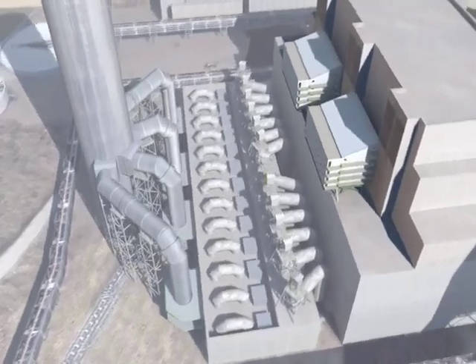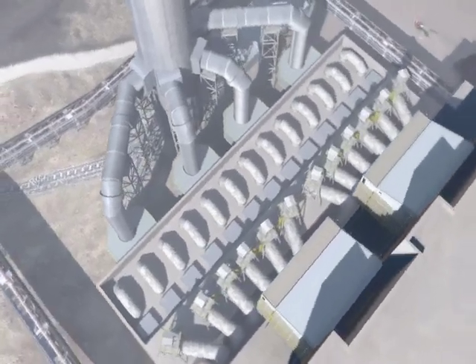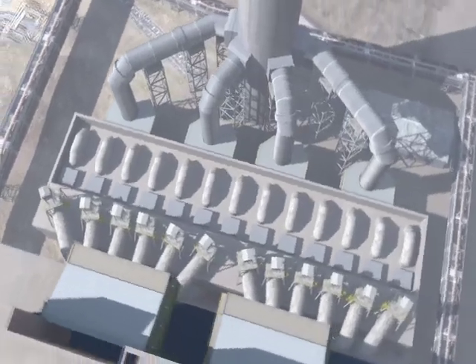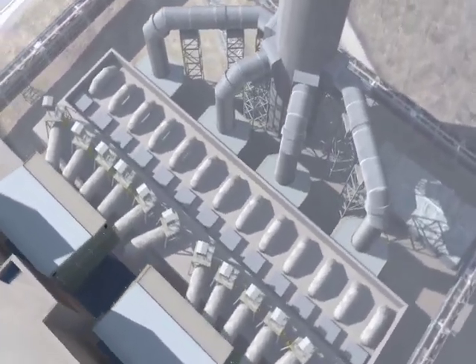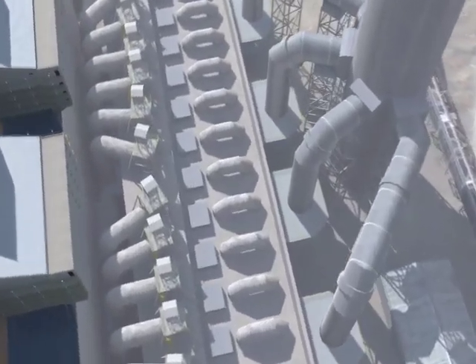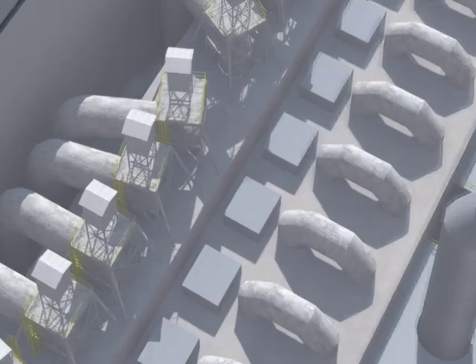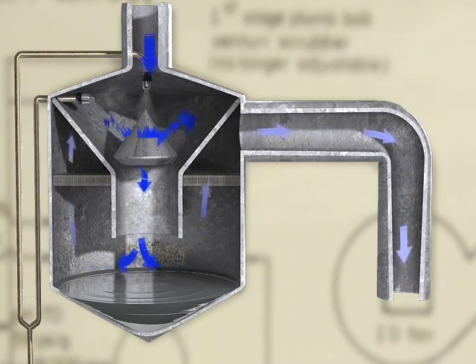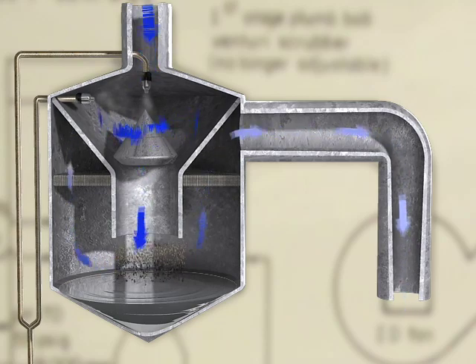Since 1971, First Energy has spent more than $5 billion on environmental protection. Our plants are equipped with air quality control systems to remove sulfur dioxide and particulates called fly ash. Fly ash is removed by a mechanical process, and sulfur dioxide is removed with a chemical reaction using lime. These processes take place in large ductwork scrubber trains located between a unit's boiler and its chimney.